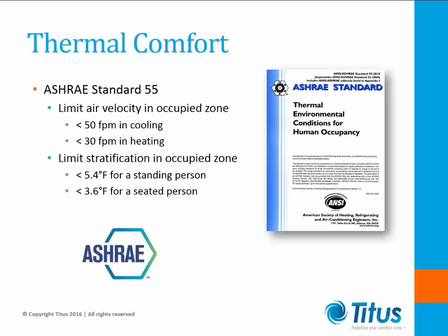First of all, how do we define thermal comfort? ASHRAE Standard 55 defines thermal comfort in terms of local air velocity in the occupied zone and temperature stratification. Excessive air velocity creates a feeling of draftiness that we sense on our skin. As a general rule, velocities above 50 feet per minute in the occupied zone are to be avoided in cooling situations. During heating, we are more sensitive to drafts, so we need to keep velocities below 30 feet per minute.